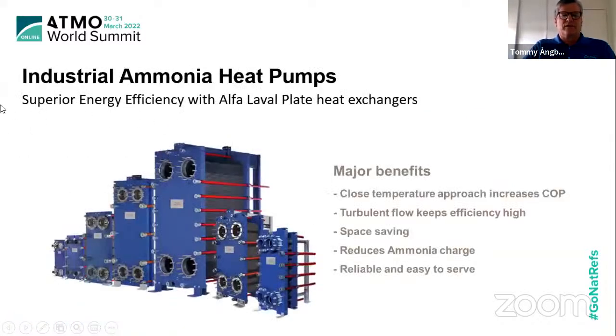So, a summary of the benefits. What I'm saying now is that you have to look at the lifetime, you have to look at the operation over time, and when it comes to heat pumps, efficiency is what pays back the investment. It's energy here. It's important to have superior energy efficiency. This is possible to obtain with plate heat exchangers because we have a close temperature approach. We have a turbulent flow that keeps the efficiency high over time and also cleans the unit. They are compact, so we can save space. We can also integrate different functions into one heat exchanger, keep the ammonia charge low, which is always a target, I think, as we have this media, and it's reliable and easy to service over time. That's what we call superior energy efficiency.